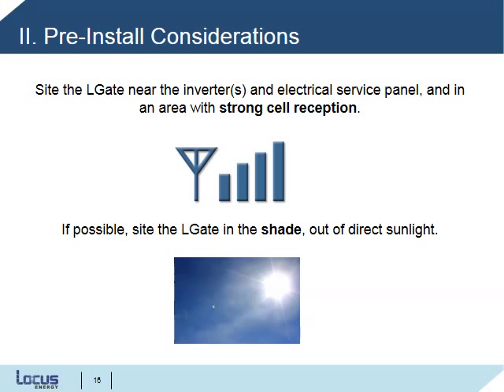Another important pre-install consideration is where to site the LGate. We recommend siting the LGate near the inverters and electrical service panel in an area with strong cell reception. Keep in mind that building interiors can weaken the cell signal. A good rule of thumb is to install the LGate where you would expect to get a signal on your cell phone. We also recommend siting the LGate in the shade and out of direct sunlight whenever possible.